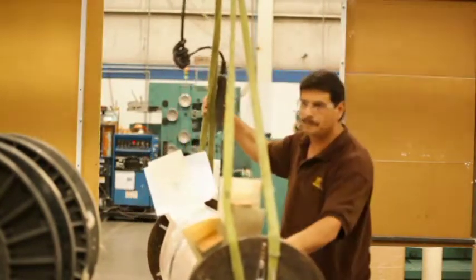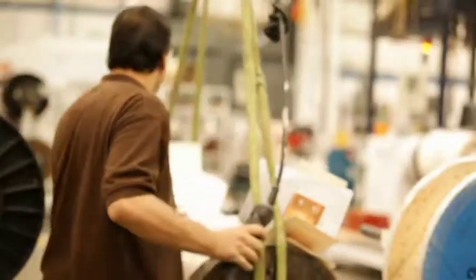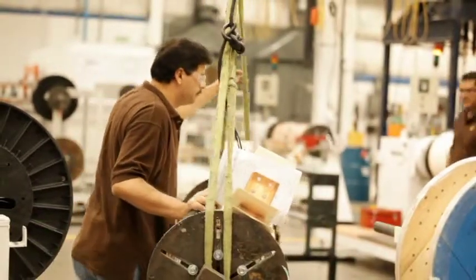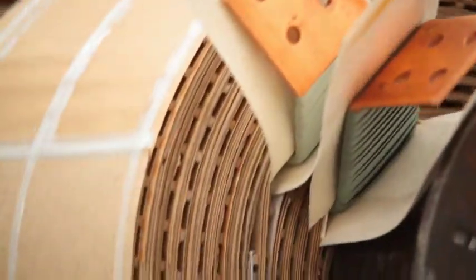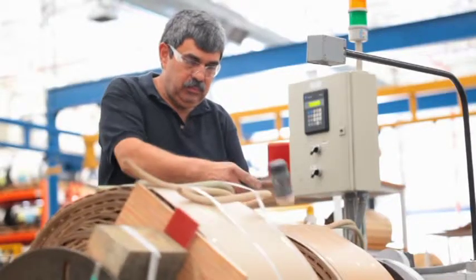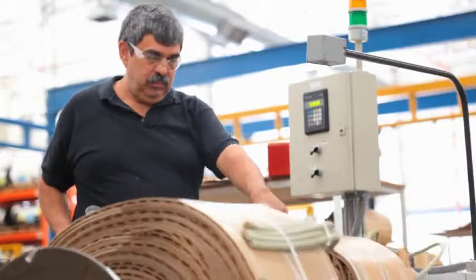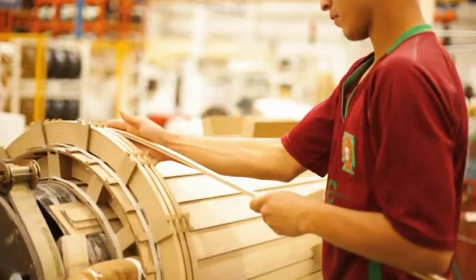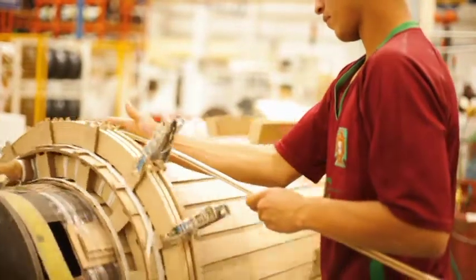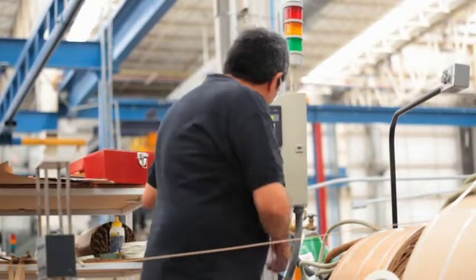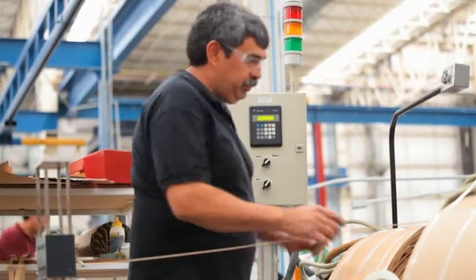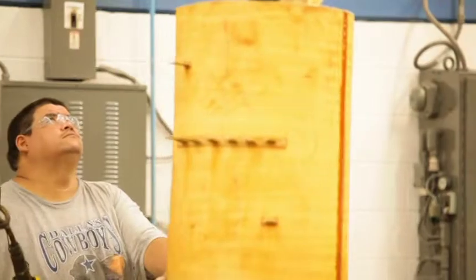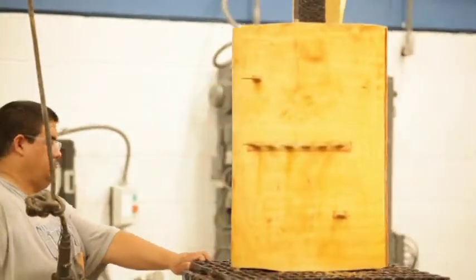In this area, high voltage windings are constructed using electrical grade copper or aluminum, covered with Nomex paper coated for dry type units or with kraft paper type for oil units. The staff has the necessary training to follow exactly the instructions stated on the electrical design drawings and instructions. Once the coil is wound, we continue to our encapsulating sealing processing area.